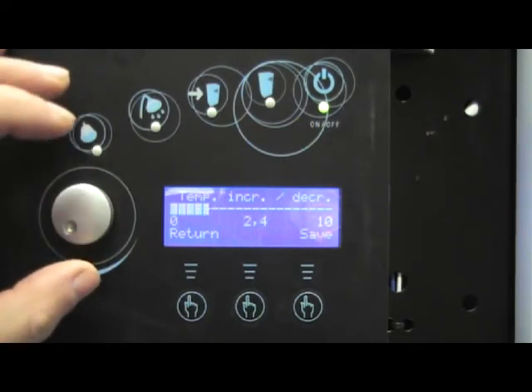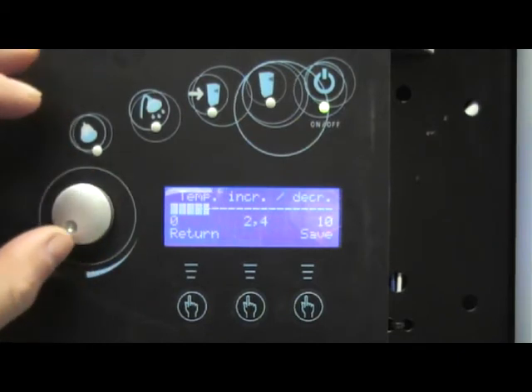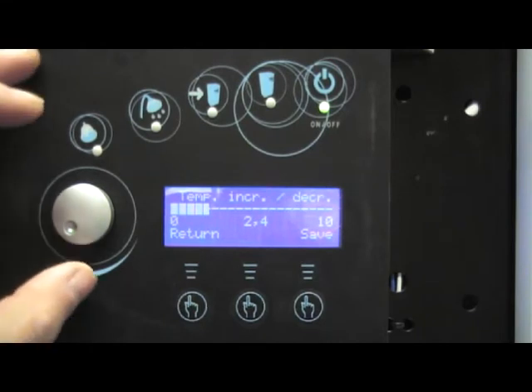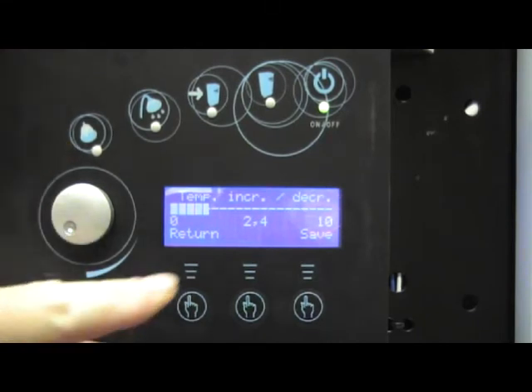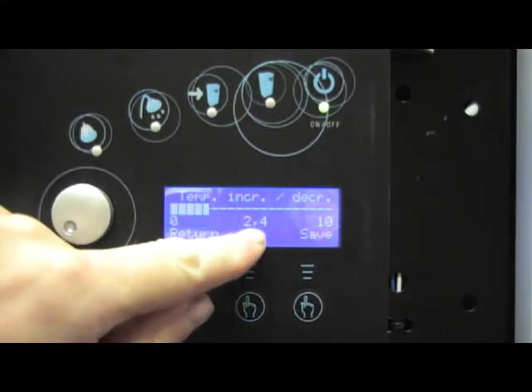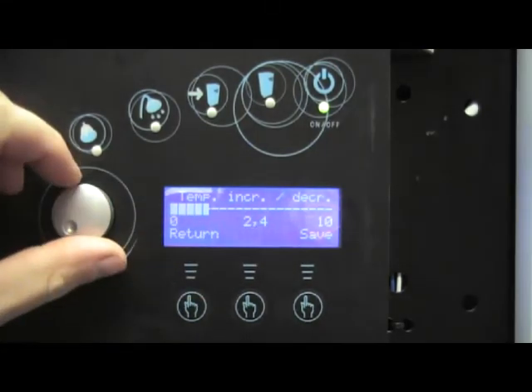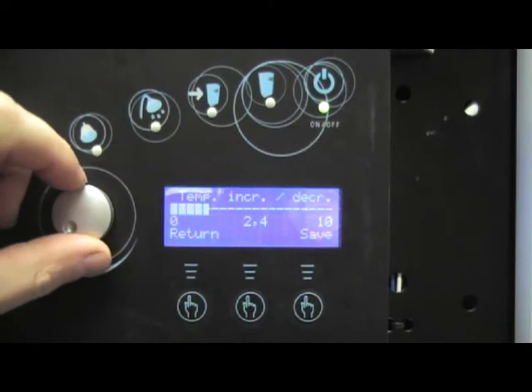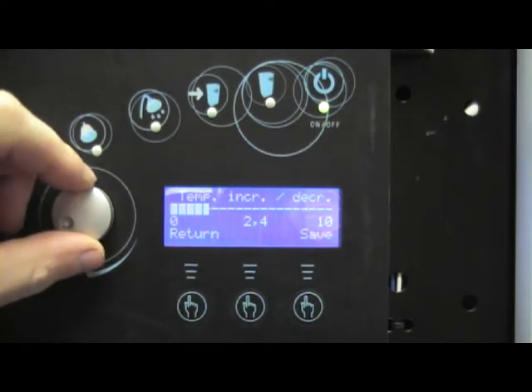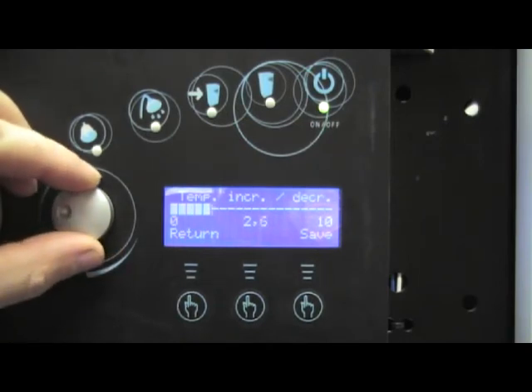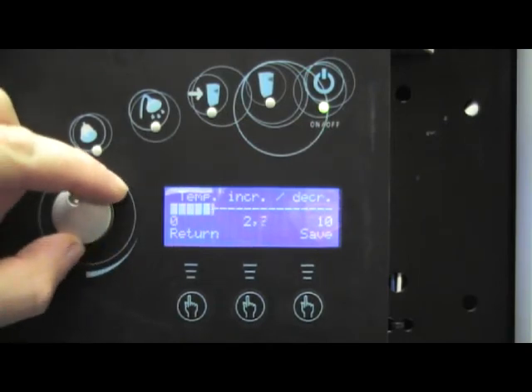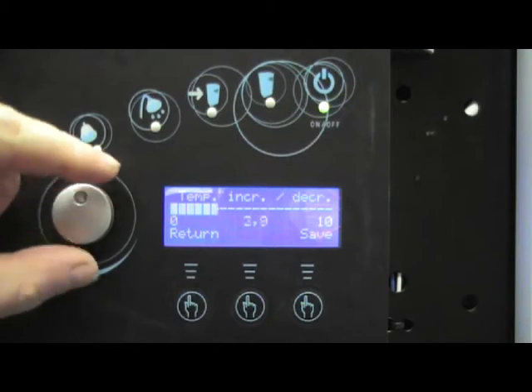For a system that is connected to underfloor heating, we typically want to have a figure of between 2 and 4. In this case, we decide that the house isn't quite getting warm enough, so we are going to change this figure to 3.